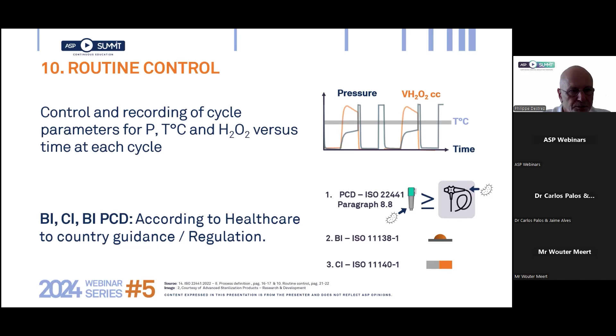Next slide is about load release. As we said before in the routine control, load release is always at least based on process parameter verification. I'm repeating again, but the standard itself does not impose the use of BI, CI/BI or BI PCD, because it's considered a matter of local regulation. But it doesn't ignore these essential accessories, obviously. Regarding the use of BI, the opposition is often made between so-called parametric release and BI release. I don't think this opposition is justified.